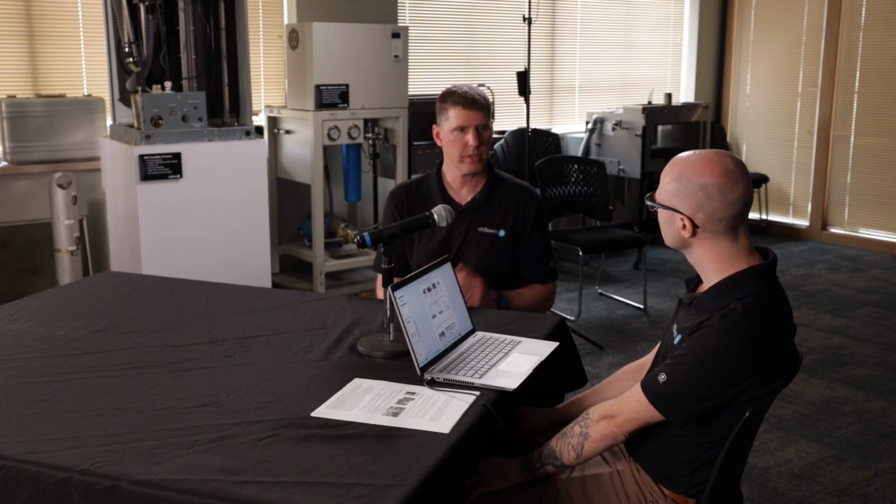If you don't have a boiler and you're working off a generator, then understanding where the condensate is going to get out of the system matters. Water's naturally going to fall downhill, so gravity is going to be a key piece. If it's close by, can I pitch it back into the generator and it dumps back in the tank? Or is it going to go towards that dispersion device?